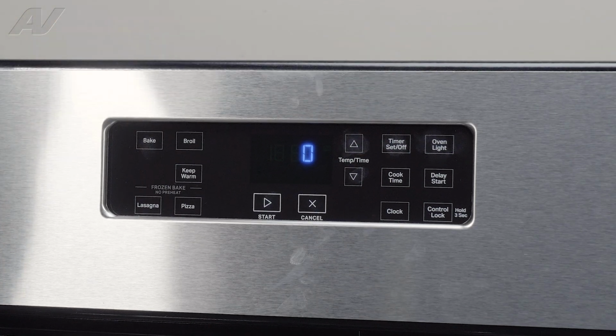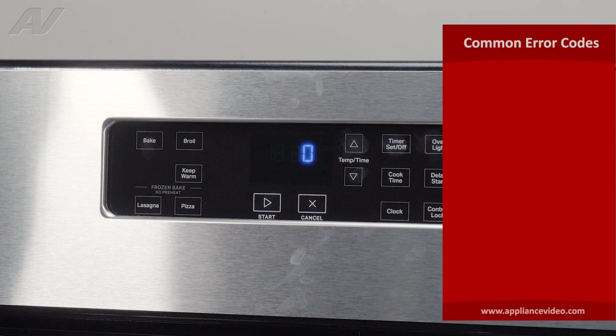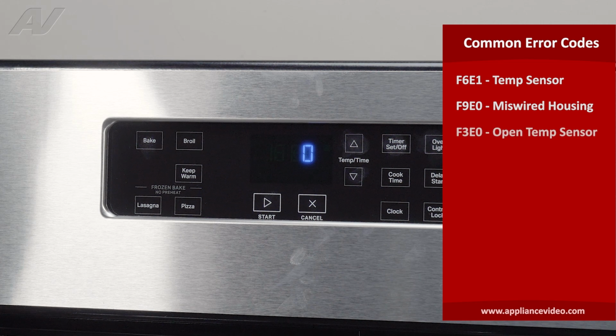So if we press it again, right here, this is where it would tell us our first error code in the system. Now, refer to your tech manual. The most common error codes you might find would be an F6E1 for a temperature sensor. You may find an F9E0 for a miswired housing. You may find an F3E0 for an open temperature sensor, or you may find an F2E1 for a shorted keypad.